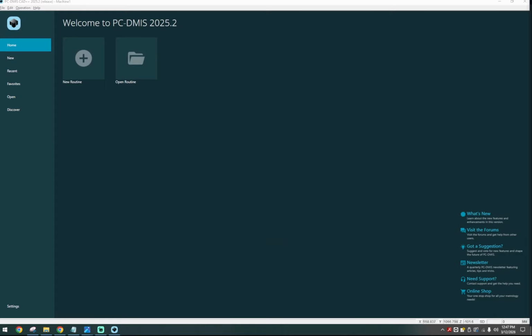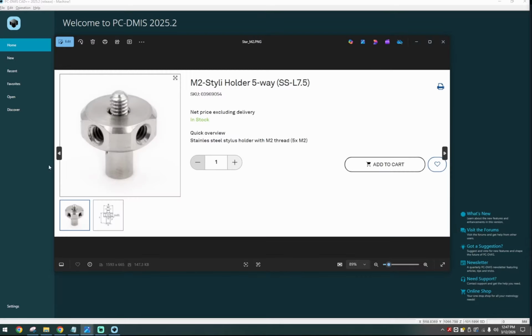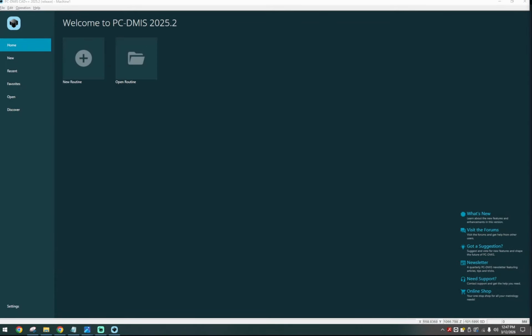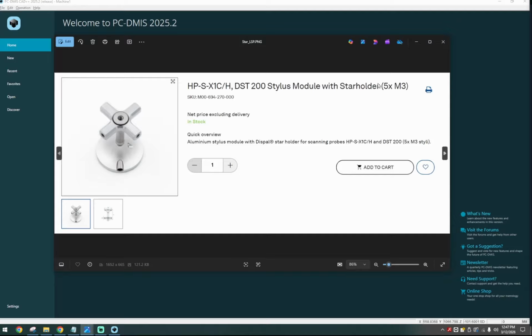To start, what is important is making sure that your CMM has the probes be square in your machine coordinate system. That way, when you're probing, you can ensure that you can get to your proper features without shanking out. For this particular one, what you do is you tighten this little bottom piece. There's a little adapter piece you can shove through this little hole, and that allows you to tighten it down and get it square. And the last one is the X1 probe. Again, there's a little Allen key that goes right here, and this is how you square it up.